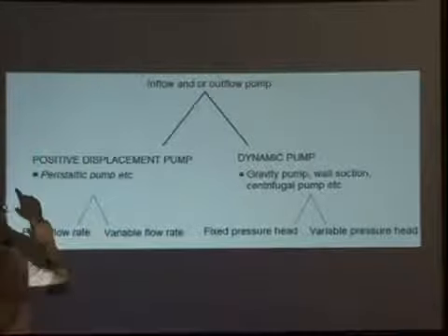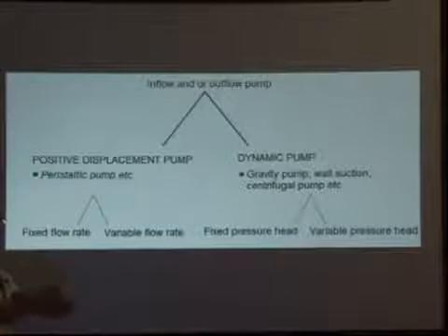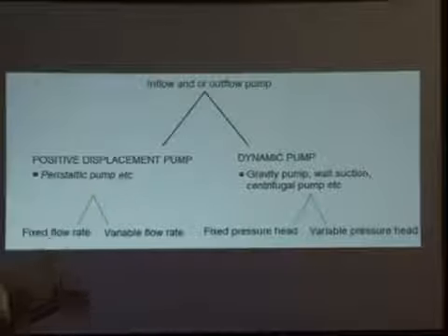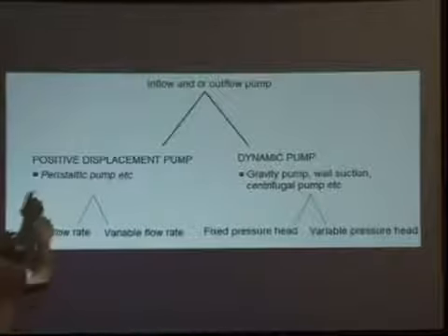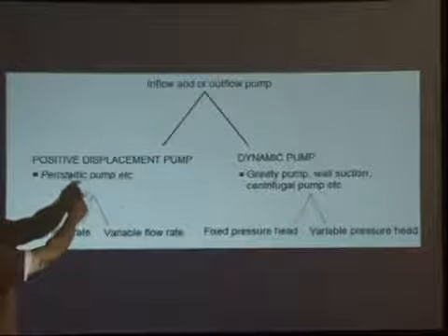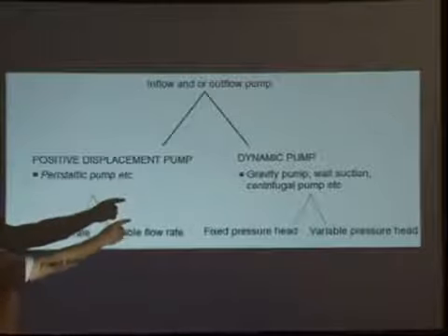The pumps are only and only of two types. The positive displacement pump, like the cycle pump by which you fill the tire, and the dynamic pump, which you have in the wells. So there is the peristaltic pump on the inflow side, and the dynamic pump, that is a centrifugal pump or a gravity pump, on the outflow side.